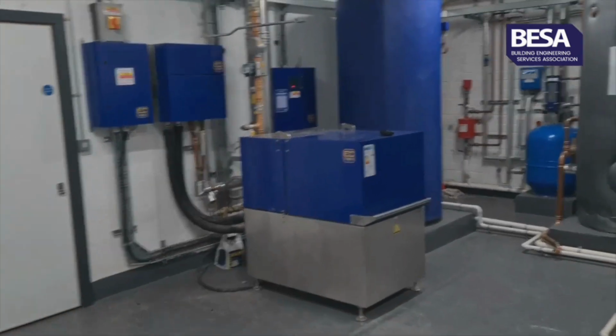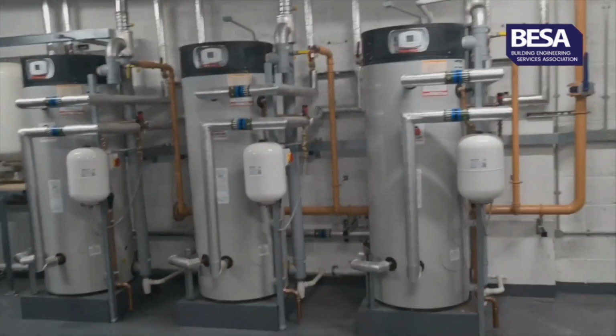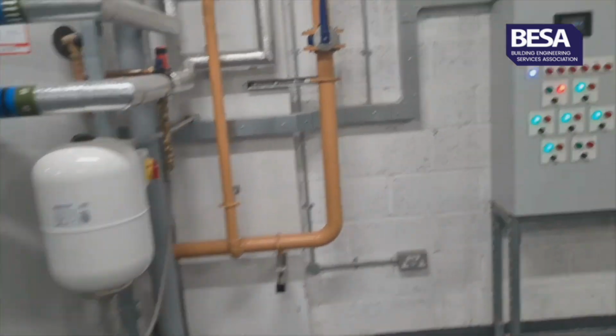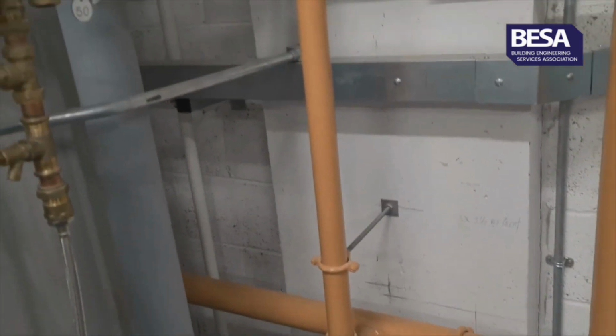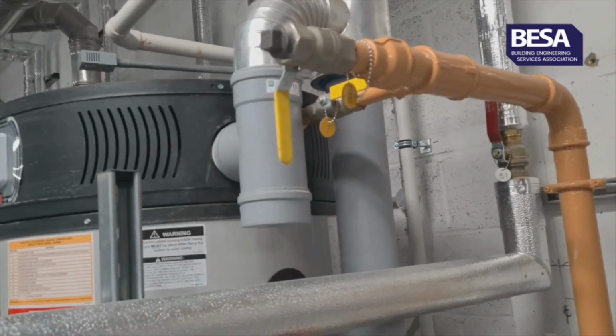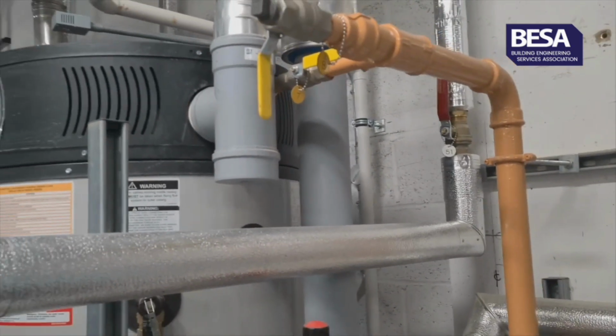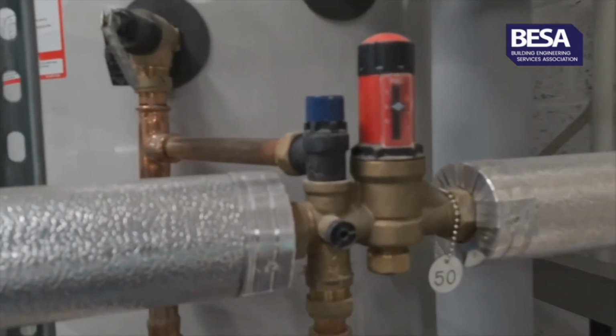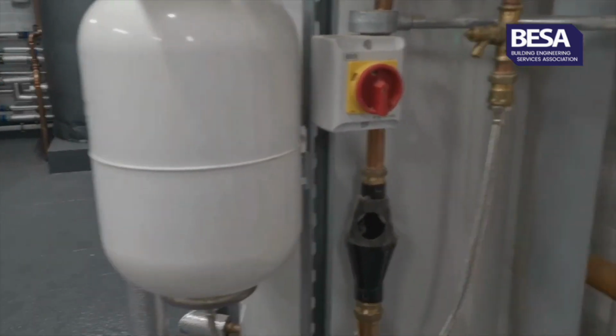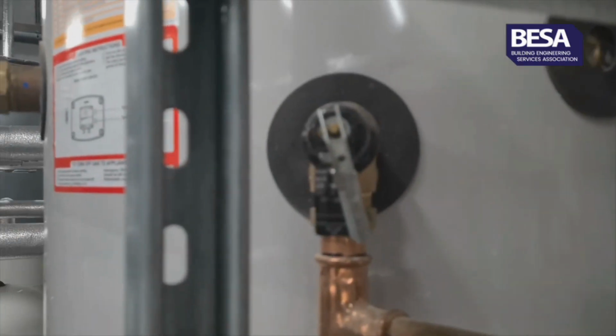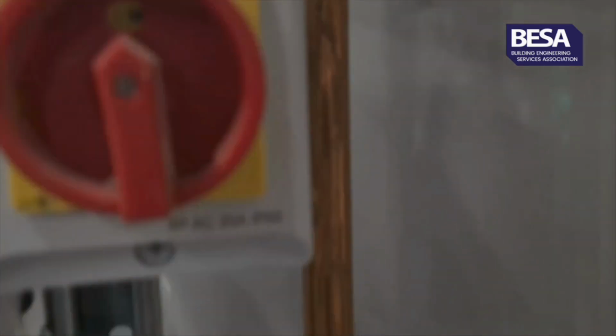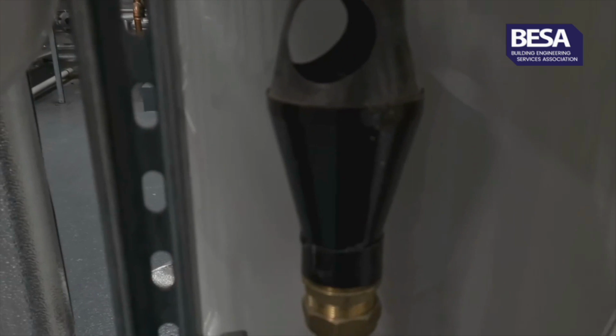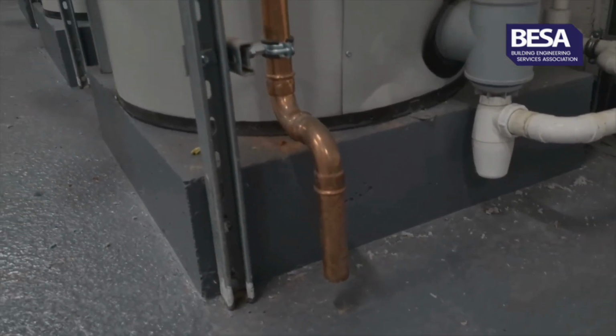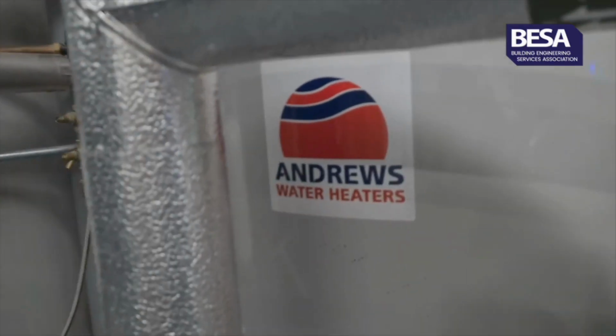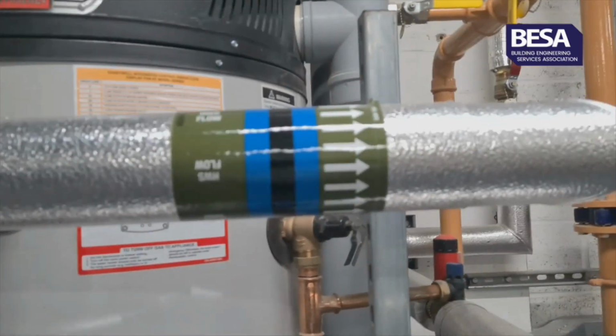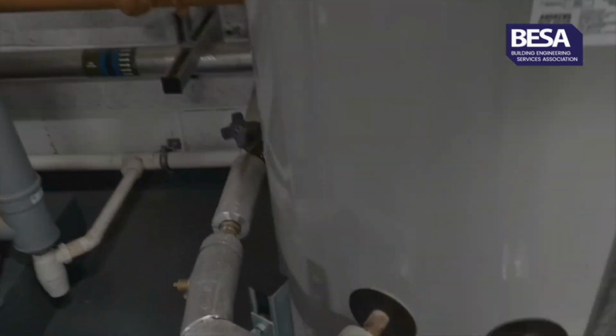Okay, so we come to the HWS generating plant. We've got the CHP, and we also have 3 gas-fired water heaters. So looking at the water heaters, first of all, that's our incoming gas. Again, these have all been installed to Building Regs Part G3, which is non-domestic gas safe certification. Here we've got temperature pressure relief valve, flexi hose into the expansion vessel, and that goes through and picks up the same pipework, feeds into the pipework for the safety valve. Copper all the way down to a nicely installed tundish, again all nice and rigid, and that then terminates onto the floor. That's the same for all three of these water heaters. They're all Andrews water heaters, as you can see. So we've got a flow out the tank or cylinder and a return in, and that's our cold feed at the back.